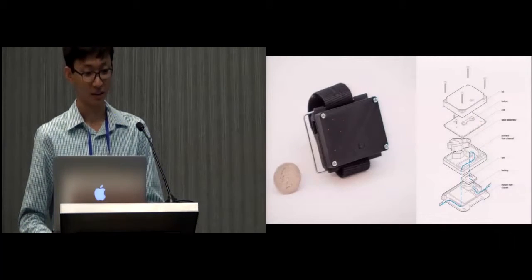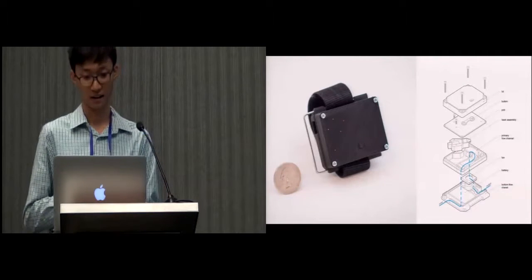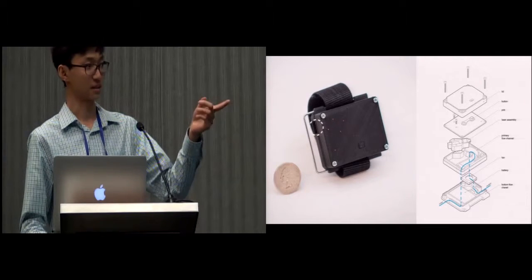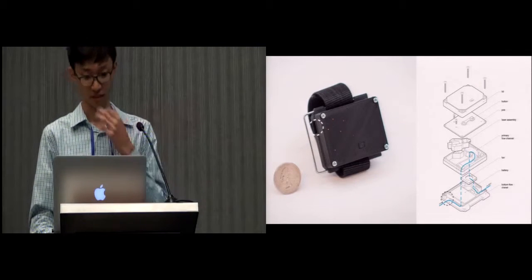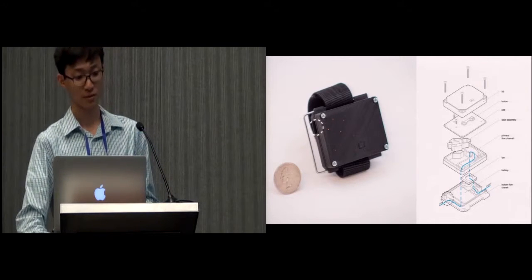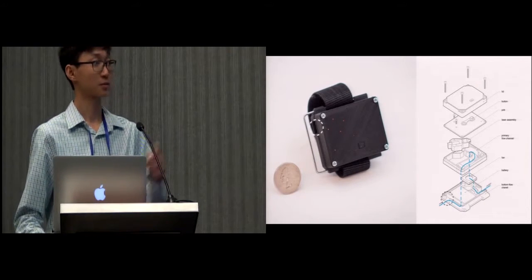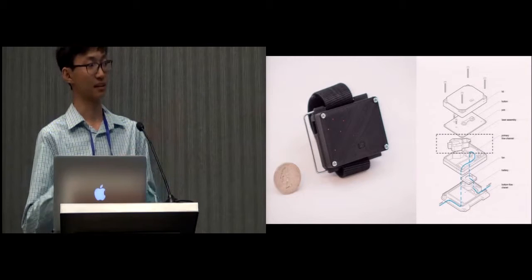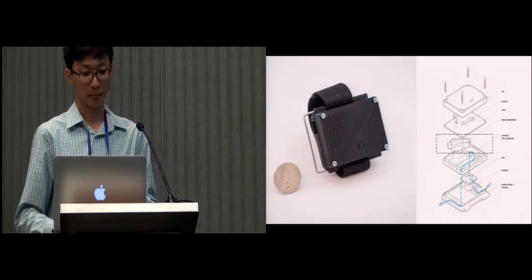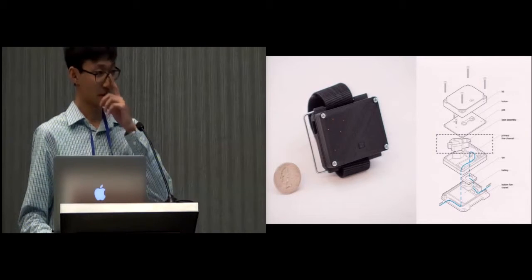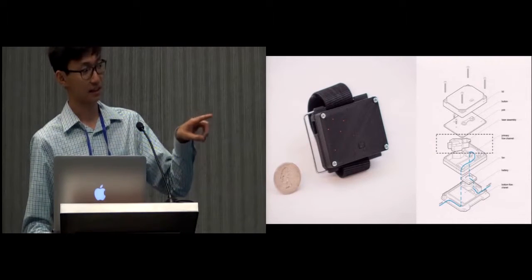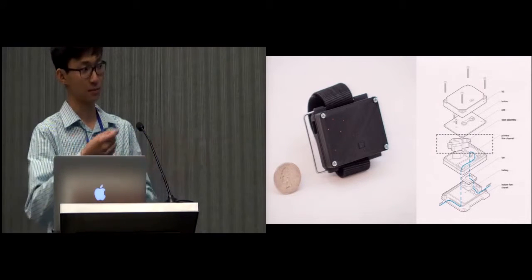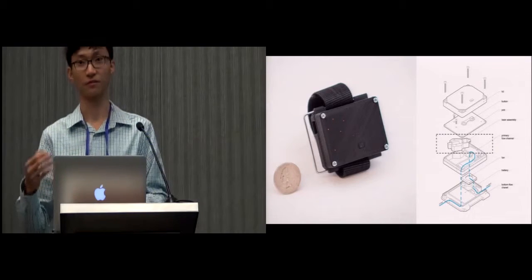Okay, so diving deeper into the mechanical design, here is an exploded view of the MyPart device. For reference, that inlet port at the left is the same inlet port that you see at the bottom left of the exploded drawing. So here I'll point out some of the most important features. To make it as small as possible, we've located the laser to be at the diagonal of our rectangular device. For ambient light rejection, the blue line indicates the path of air as it enters the system. And as you can see, both the inlet and outlet have these bends and turns that prevent ambient light from directly entering the system.